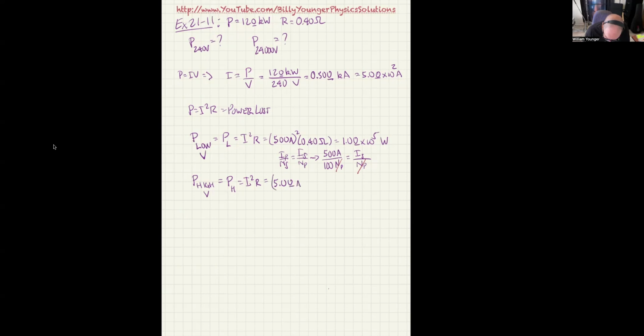And that quantity is going to be squared, and it's still times 0.40 ohms. So in this case, we're going to get 5 squared times 0.4, which gives me 10.0 watts. So you can see basically it's a factor of 10,000 more power when we use the low voltage than when we use the high voltage.